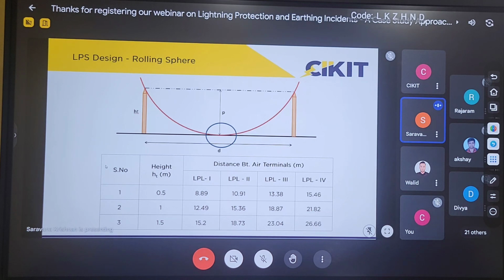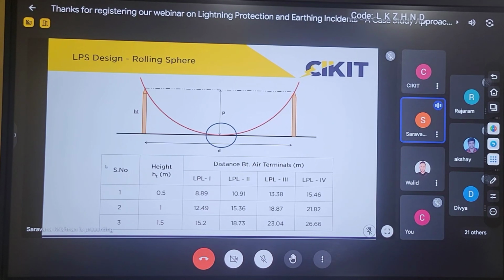Also, if I am performing the calculation using different methods like the protection angle method and the rolling sphere method, obviously the number of air terminals required will be different because they are completely different methodologies. It is an enhanced method, so there will be some difference in the number of air terminations also.